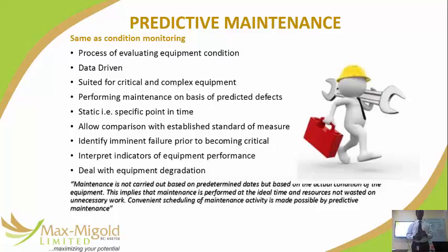every day. Now, at some point, you will see it going out of parameters. Take temperature, for example, or vibration. It's going out of range gradually. Okay, it's 27.5, 27.7, 27.8, 27.95. You understand?